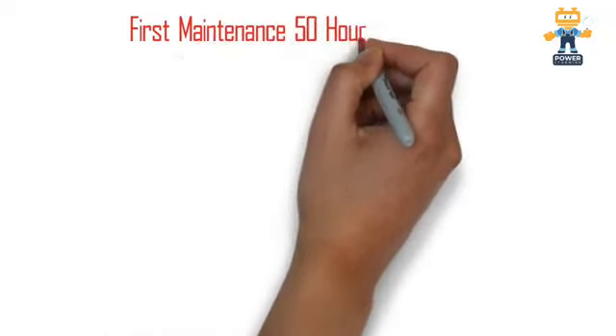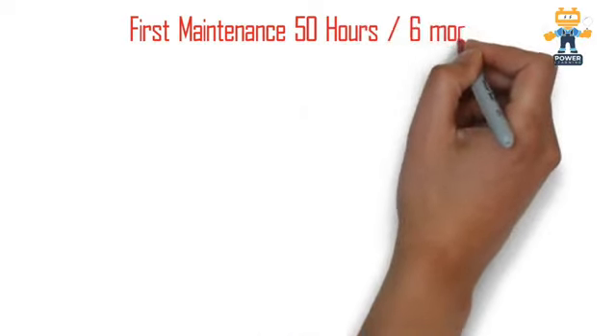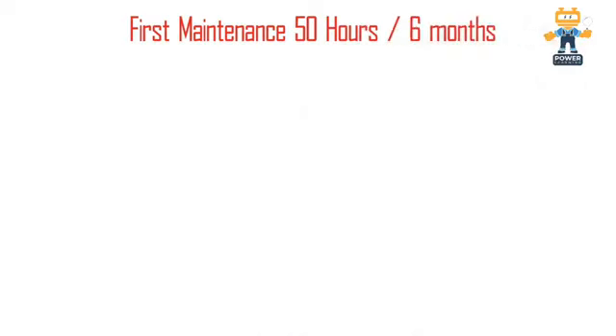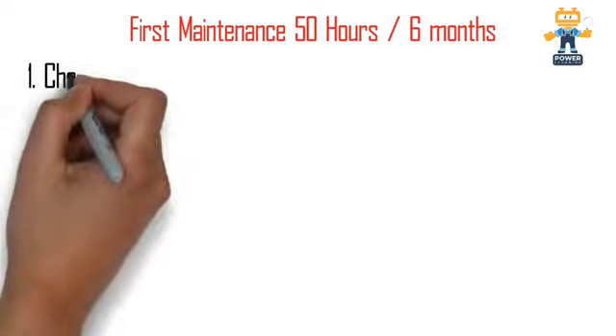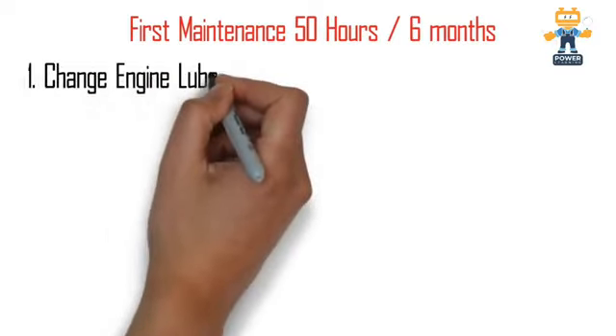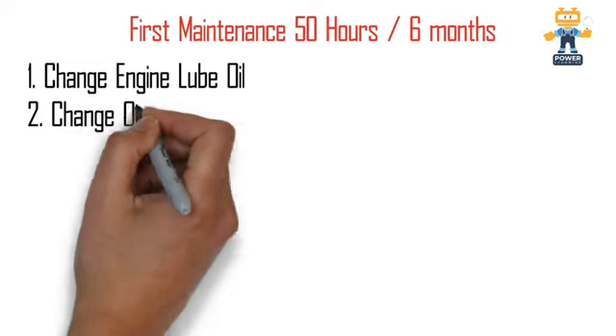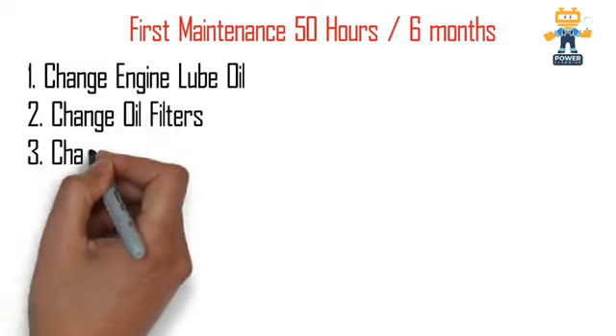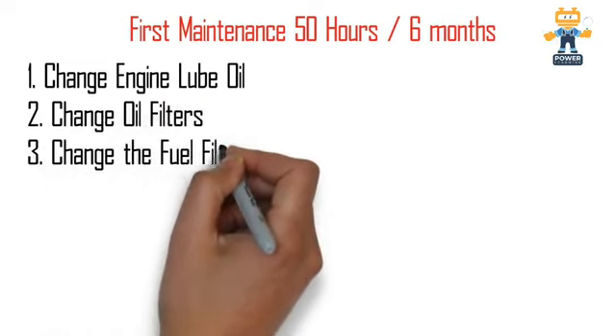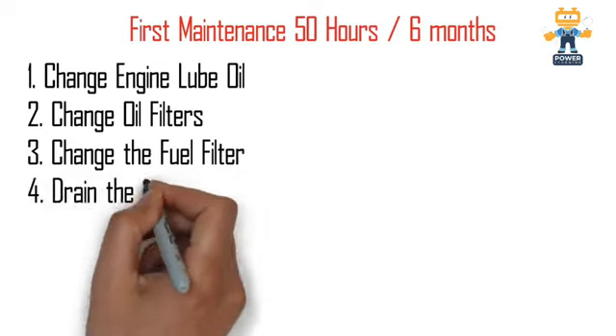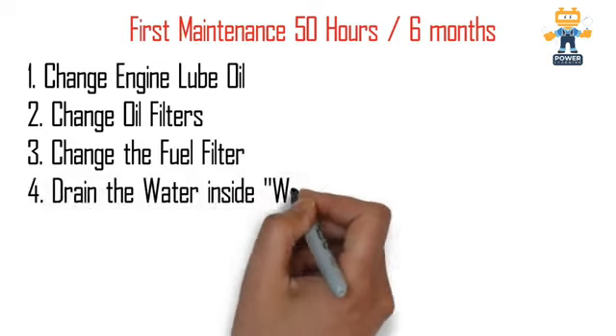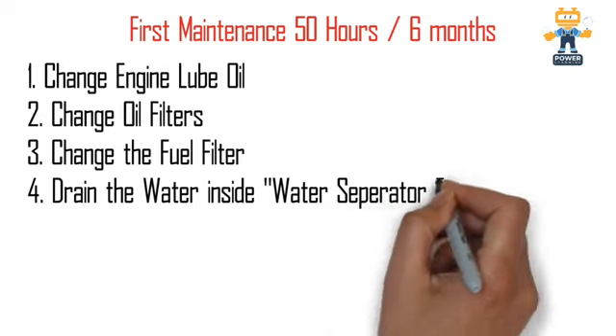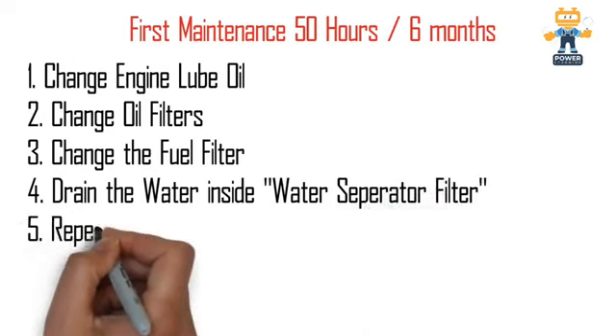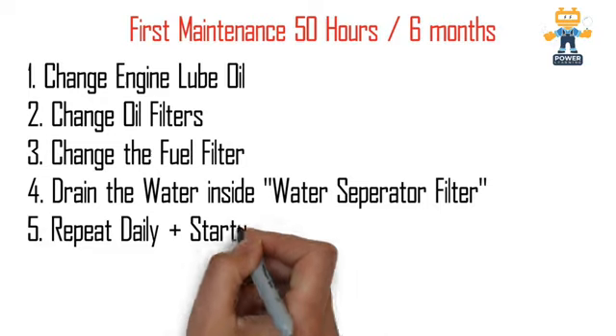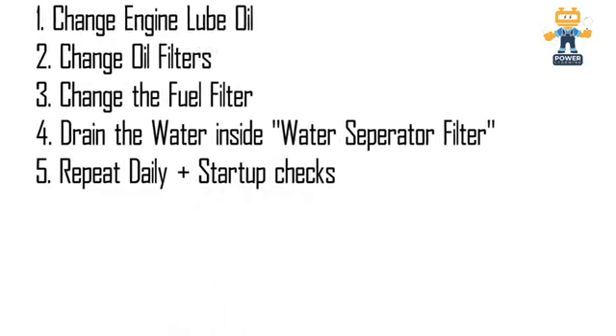Now we will see the first maintenance at 50 hours or 6 months. If you are using the generator on a daily basis, you have to do these points at the first 50 hours. If your generator is in standby mode, you have to do this at 6 months. The first point is change the engine lube oil, change the engine oil filter and the fuel filter also, and drain the water from the water separator filters. Number 5, repeat the daily and startup checks, which we already discussed before.